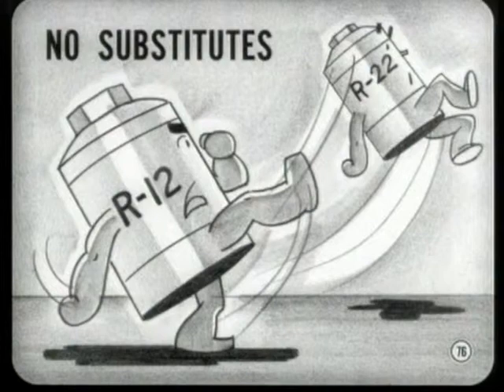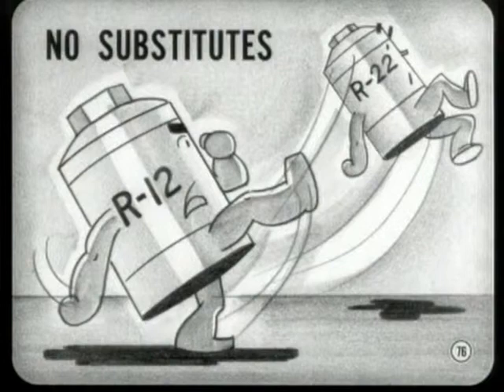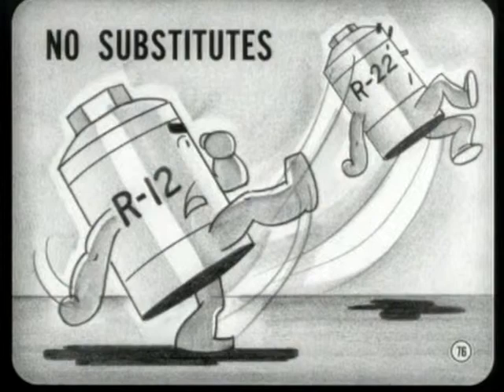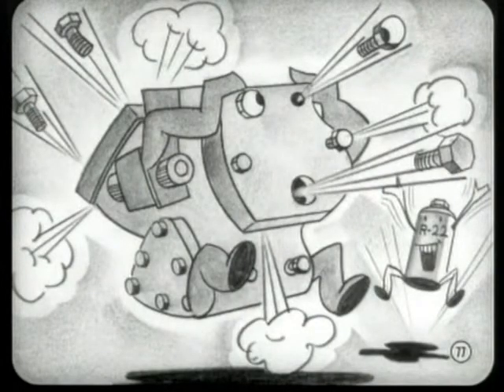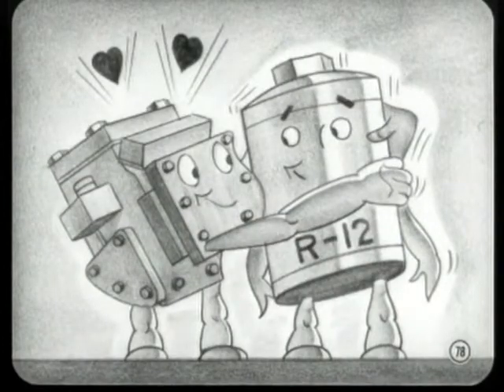Let me interrupt here, Gene. I've heard some reports of independent air conditioning specialists substituting refrigerant 22 for refrigerant 12 when they recharge a system. Don't ever do it. Don't even use a partial charge of refrigerant 22 in our systems. You'll wind up with head pressures as high as a kite, and the mixture of the two refrigerants will ruin the seals and corrode the lines. Our air conditioners are designed to use only refrigerant 12. If you use anything but refrigerant 12, you're just asking for trouble.